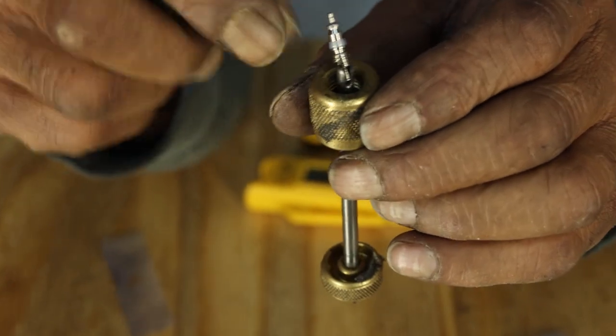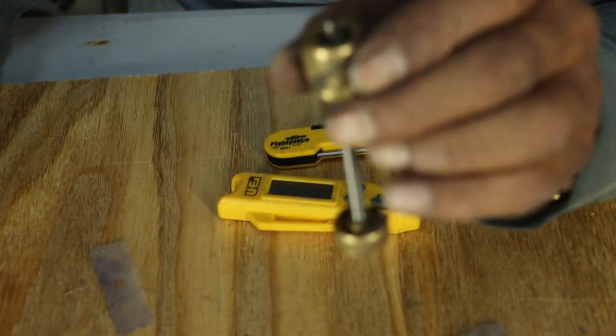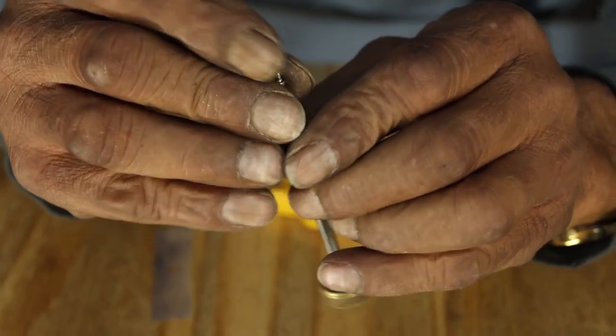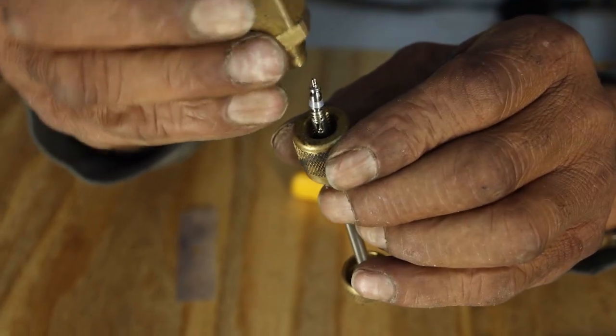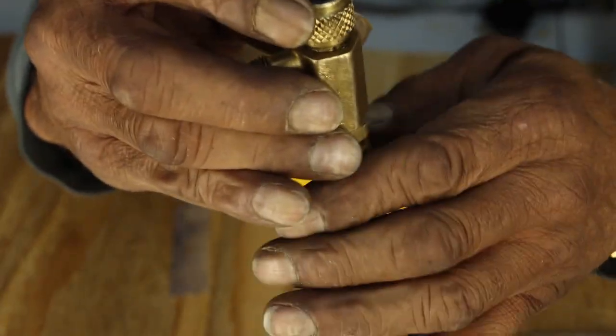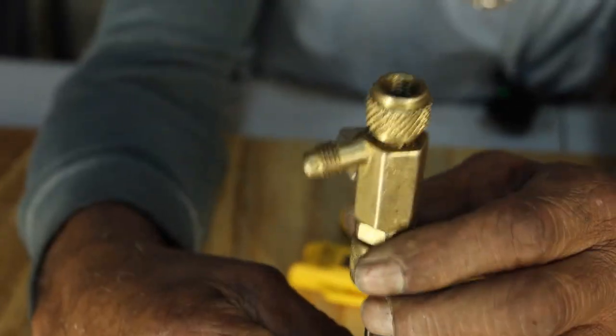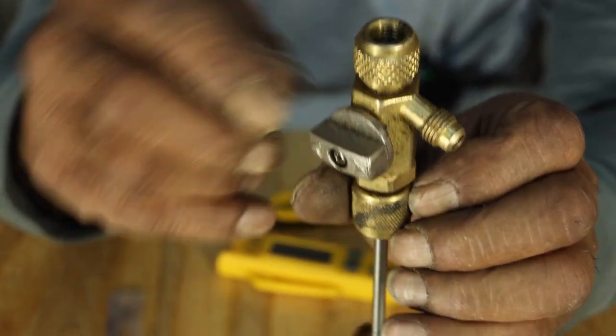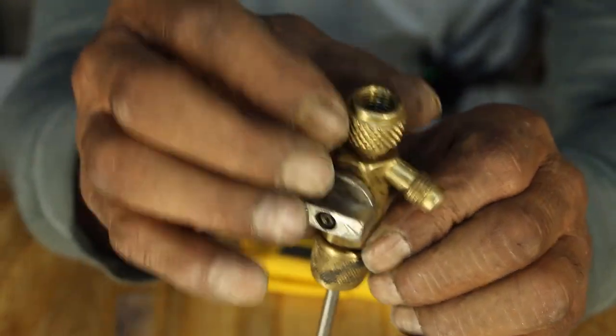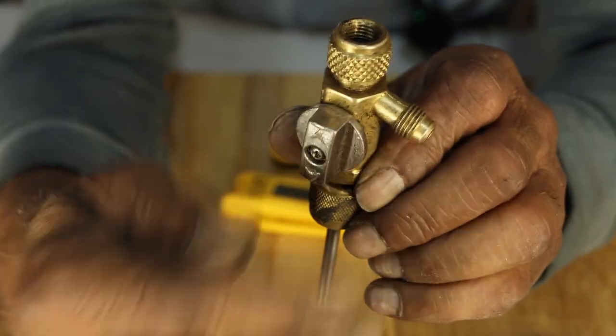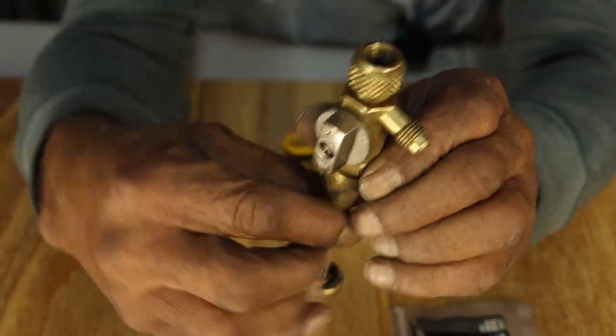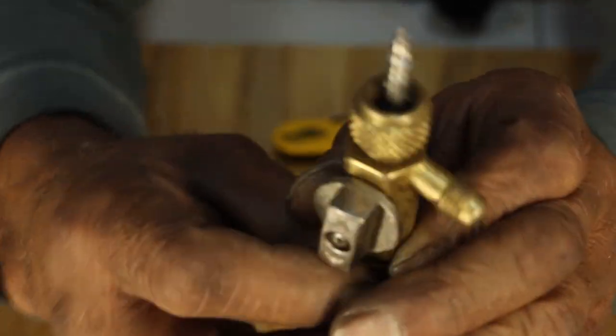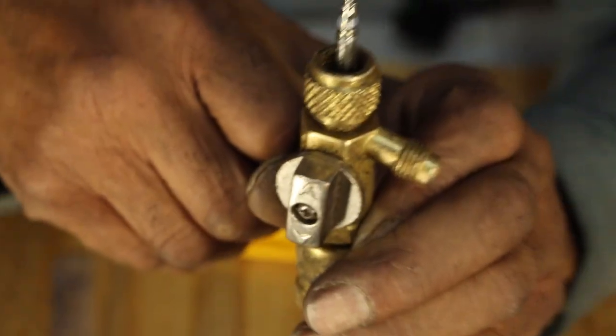and I can take the old Schrader valve that I just took out of the system. Then I can put a new Schrader valve into the system, tightening it back up so my Freon can't leak out. At that point, I can't push it through because my door is closed. But now that that's secured, this is still connected to the unit. I open this, the Freon can only come back to, then I can push my new Schrader valve in, and I never lost my charge.